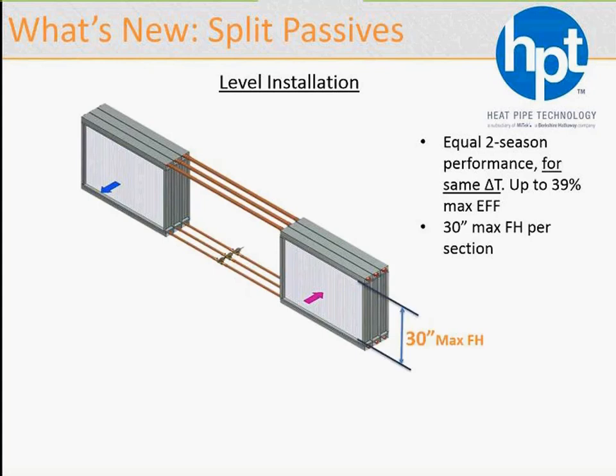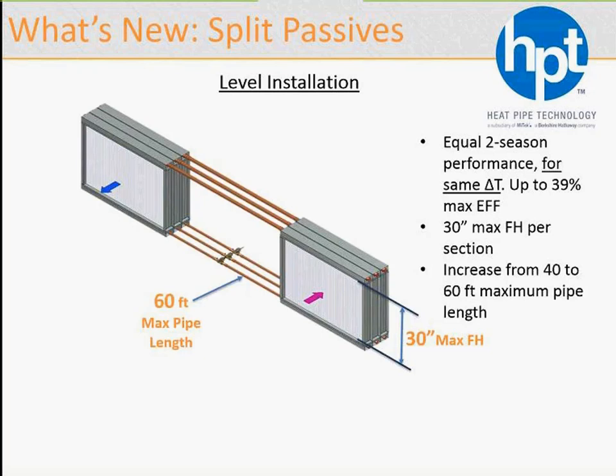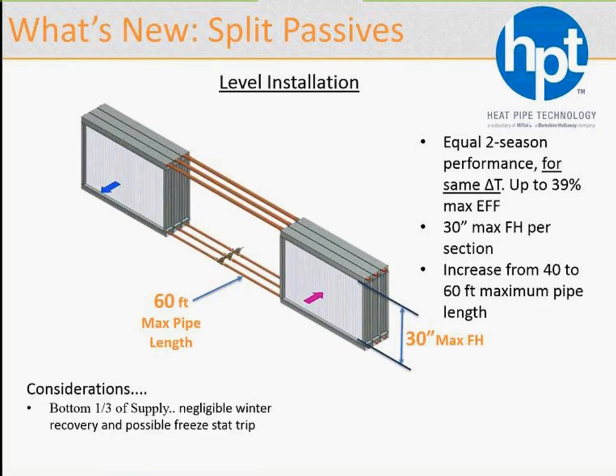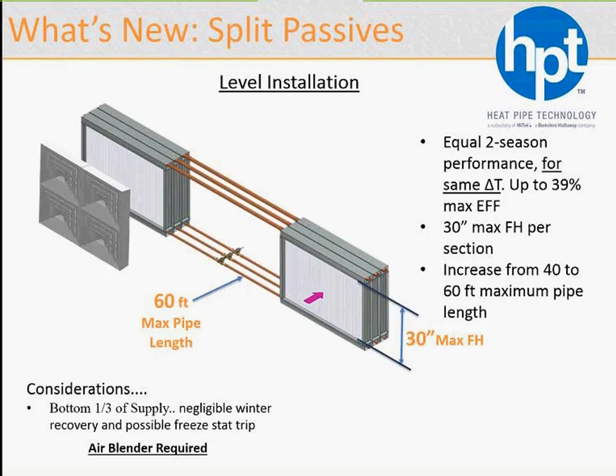Similar to the vertical DHPV, as in wraparound heat pipes, the maximum section height in this case is 30 inches, but there is a significant increase to the distance from supply to exhaust. It went from 40 to 60 feet, a 20-foot increase. That gives the engineer even more flexibility to place the supply and exhaust apart, to work around obstacles in the design process. Considerations: the temperature profile across the supply side, very similar to the wraparound heat pipes, is not uniform. So you could have freeze stat trips and so on. To prevent that from happening, an air blender is needed downstream of the supply side. So that is a requirement. In the past we mentioned it, but we believe that it needs to go on every system, of course, if you care about your freeze stats not tripping.